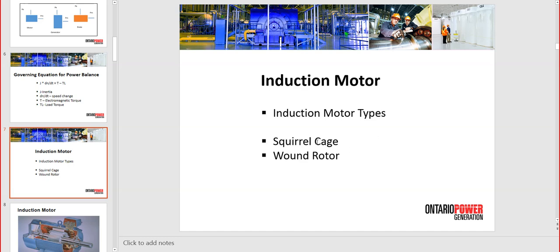Induction motor types, we have two. The squirrel cage, 90% of the time, is because we want to have a motor that is robust, no brushes, no other elements that can break down the motor. But the disadvantage of this motor is that you only supply power from the stator, so you need to have a very small air gap. So the squirrel cage bearings and everything else need to be very well maintained and aligned, otherwise there is a danger of the stator touching the rotor. And then we have the wound rotor, with access to the rotor through brushes, and it gives good control, since you can change the parameters in the rotor, adding resistors through the external brushes. That's how you can change the speed and the torque, and it is still used, but the preferred motor by far is the squirrel cage.